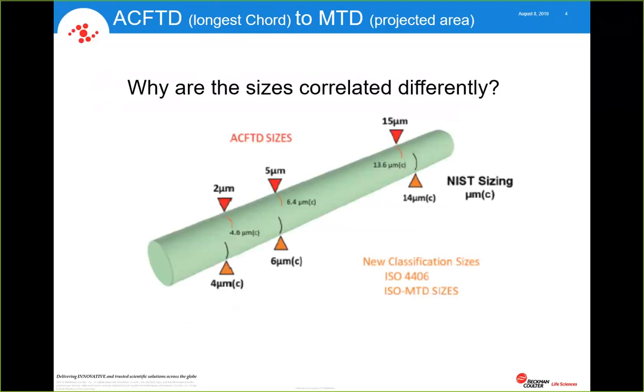So if you look at this, the old 2-micron is now sized as about 4.6 micron if you look at the center of this picture. But for the NIST sizing, it's actually sized as a 4, and so on and so forth. 5-micron is actually around 6.4, being sized MTD, is reported as 6 micron, et cetera. So that is the fundamental reason why we have to correlate the old sizes to the new, and that's with the sizing methodologies of longest chord versus projected area, why they don't match up number for number.